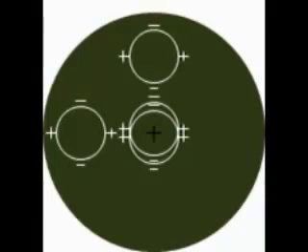Looking through the eyepiece, you will see the target mires. Note that the target mires may be blurred. If the target mires are blurred, turn the focusing knob to clear the image. The black plus sign should be in the center of the bottom right-hand circle, also known as the focusing circle.